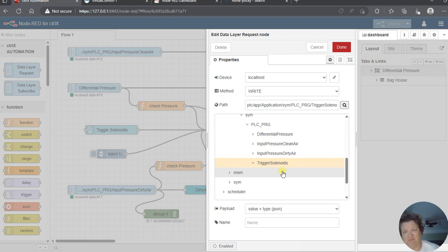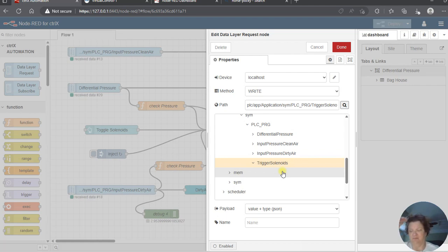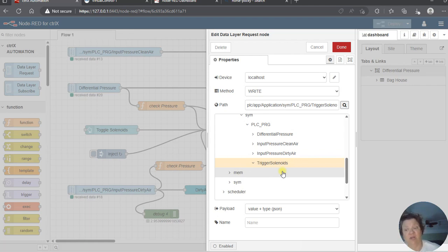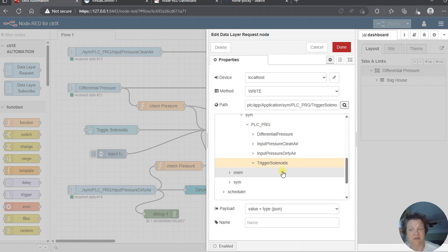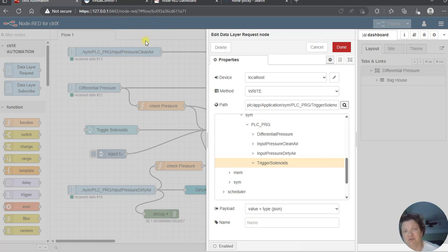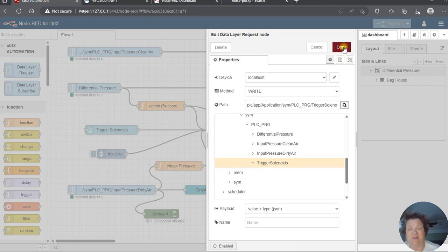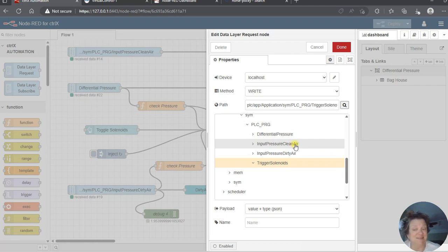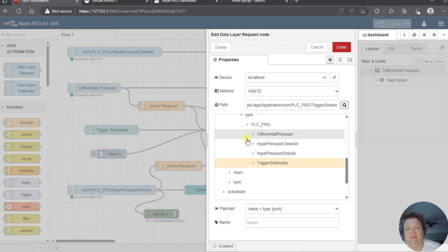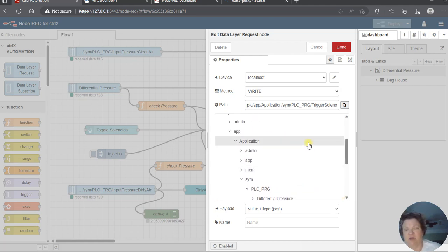So that's the way you can limit how far, if you're ISA 95 type person, how far a level two or level three's type application can drill down into your level one application for out in the field. I bring that up because of OT security. Where Node-RED resides, as far as data and display, it shouldn't necessarily be able to get to everything in your PLC unless you explicitly say that it can.